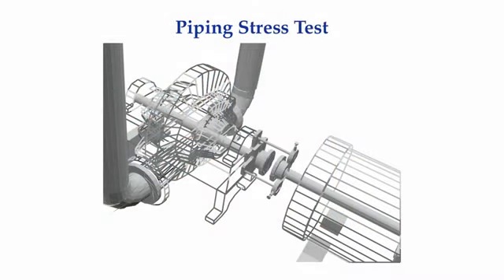When pipes are attached to machinery, you cannot visually see if there is an excessive amount of piping stress present. Prior to attaching, say, the suction and discharge pipes on a pump, one way to check for excessive piping stress is to rough or final align the machines. Attach brackets to one of the shafts, span across the coupling, and place a dial indicator on the top and another indicator on the side of the other shaft. Plunge the indicators in a little bit and zero the indicators. If you only have one bracket and one indicator, set the bracket and indicator off on a 45-degree angle.